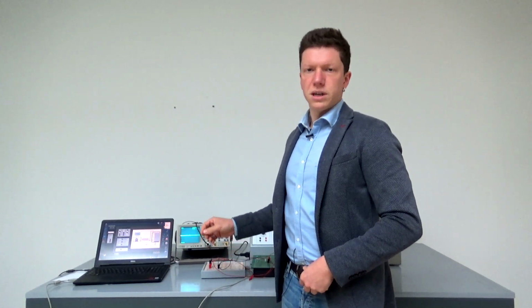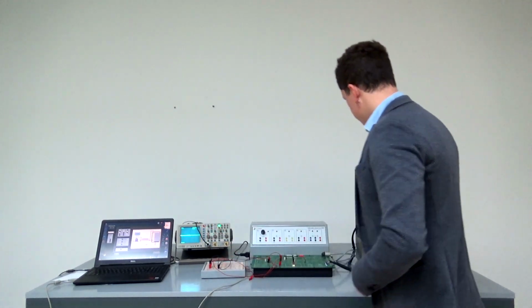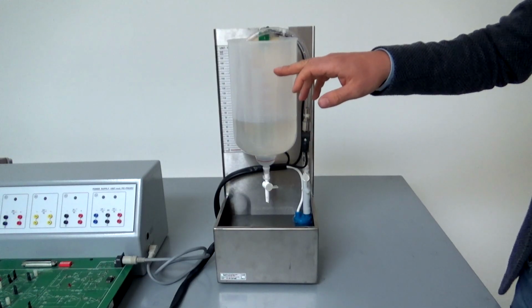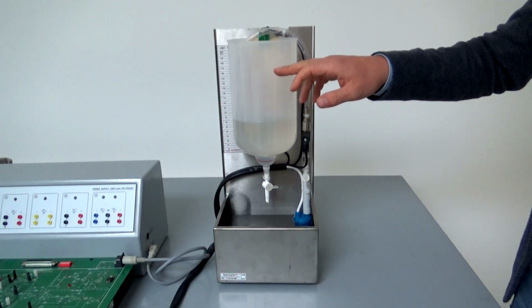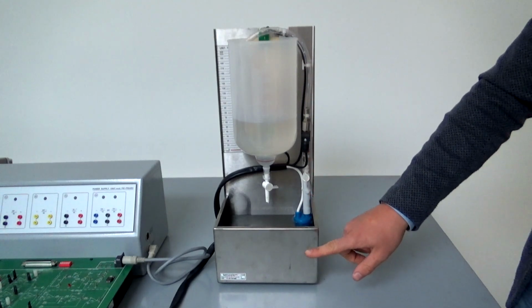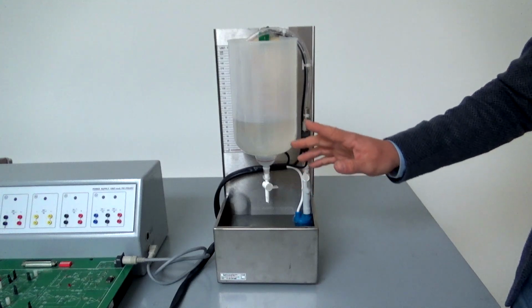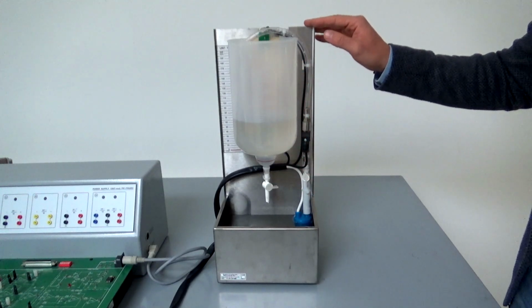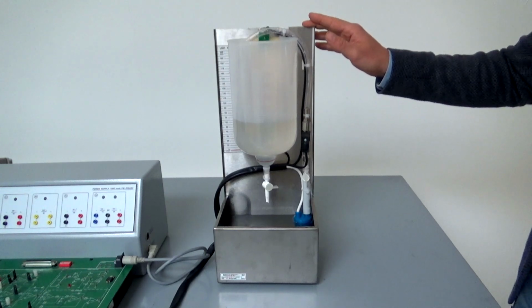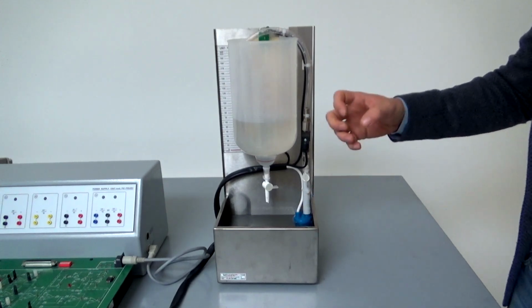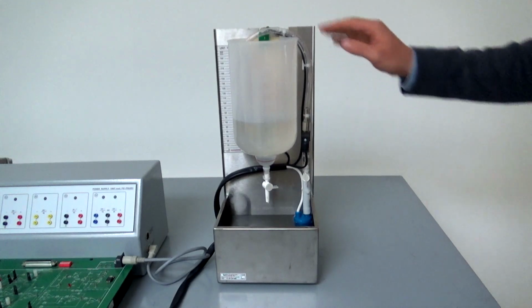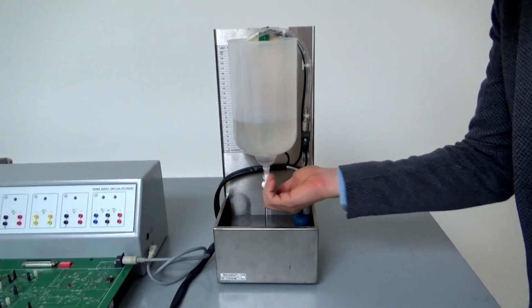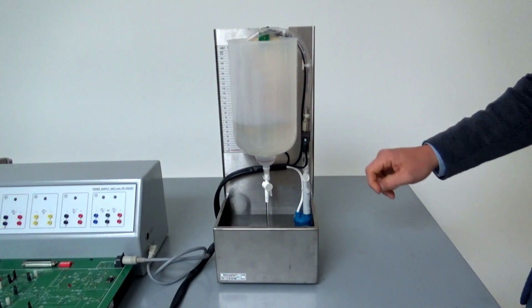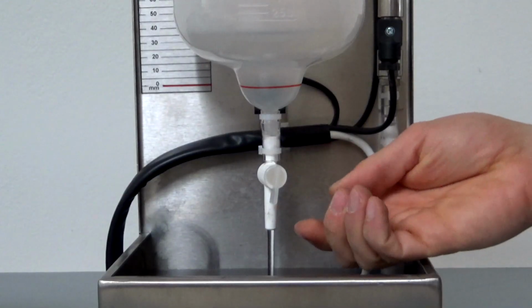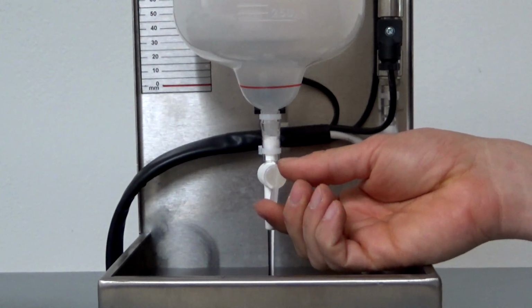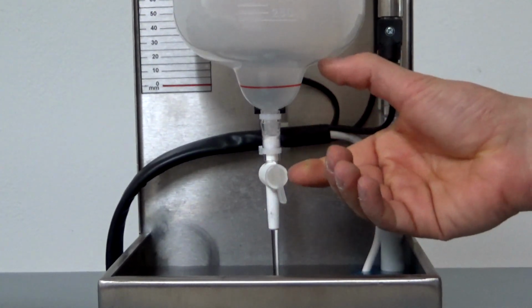So now let's perform the calibration of the 0 on the external unit. You have to fill up the tank up to 2 liters before starting the measurements, and then up to 3/4 of the lower tank. Above all, it's around 4.5 liters of water. Just enough for the pump to have some water to grasp. Then you have to open the faucet here in order to let the water drain down and regulate it until the level goes to the red line, meaning 0.